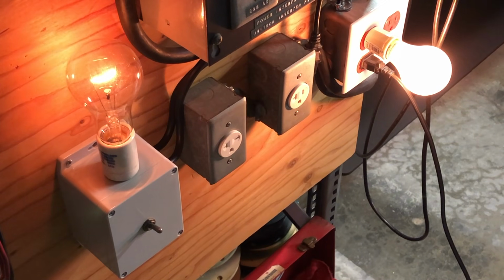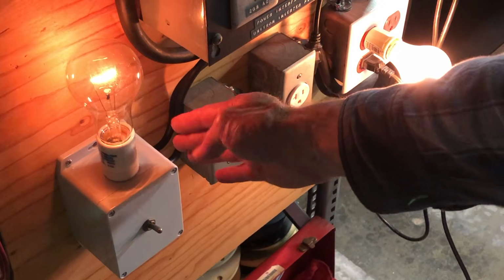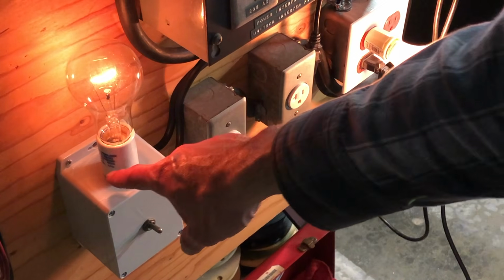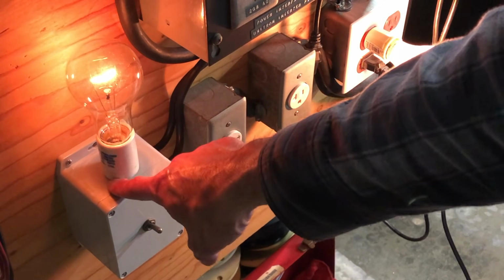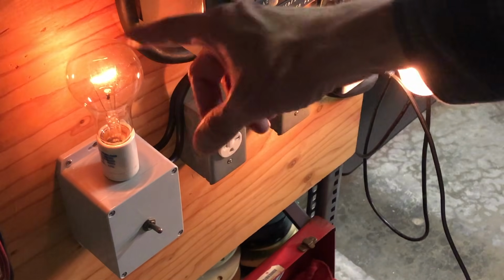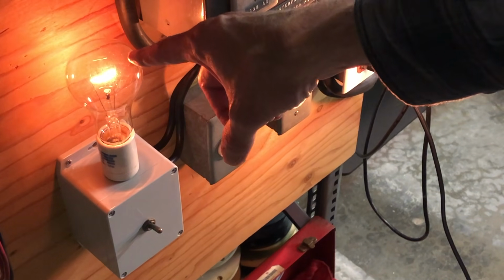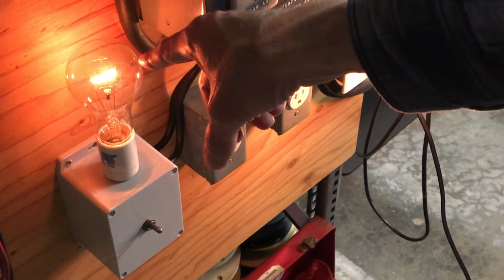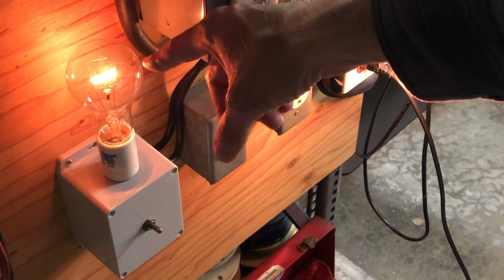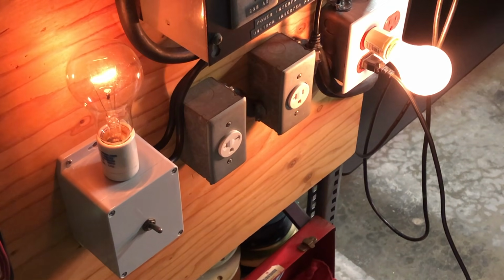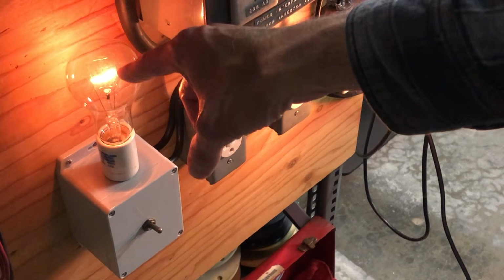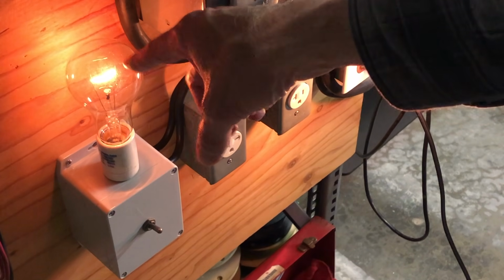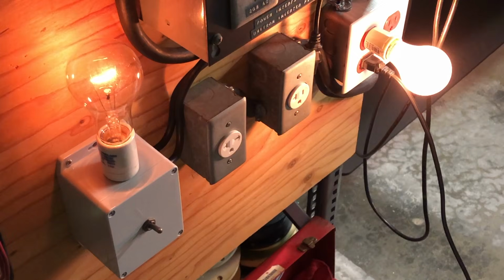Here we are looking at the final part of the dim bulb tester arrangement that I have on my workbench. So you can see here we have a switch box with a toggle switch installed and a socket on top that's permanently fixed to the top of the box. I have a 150 watt incandescent lamp that's in place right now. This can be changed to other wattages depending on the device I'm testing. It's also important to note that this cannot be an LED or fluorescent lamp. It must be an incandescent bulb.